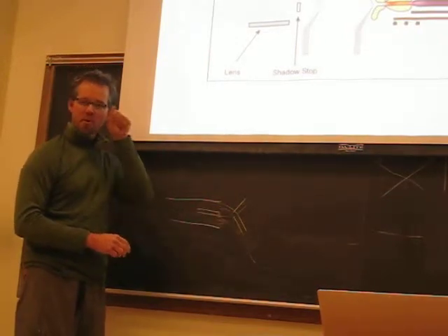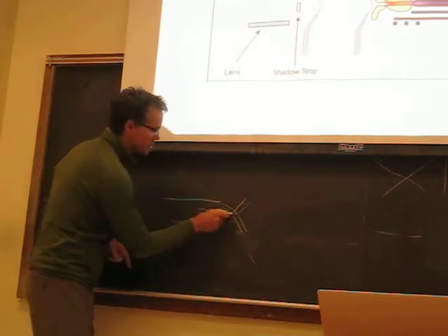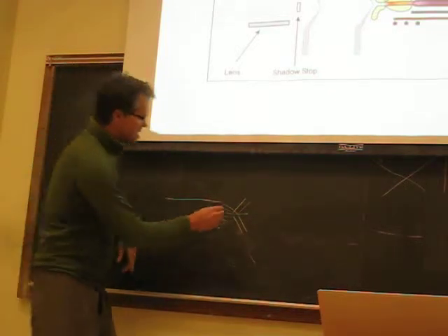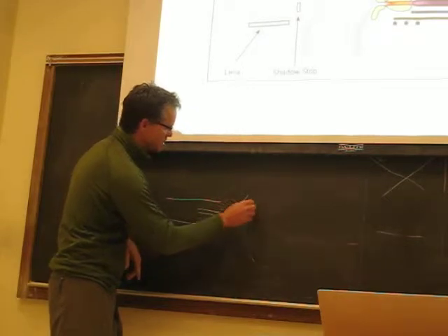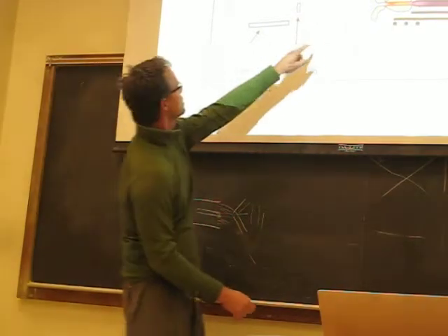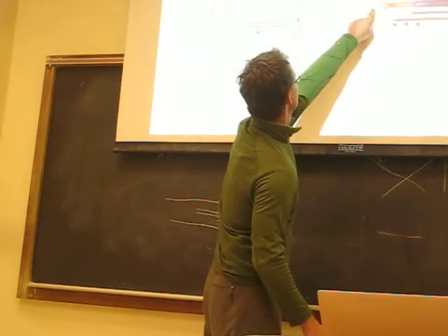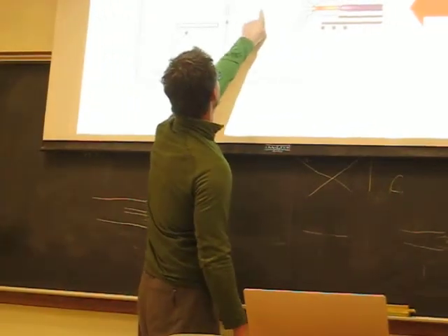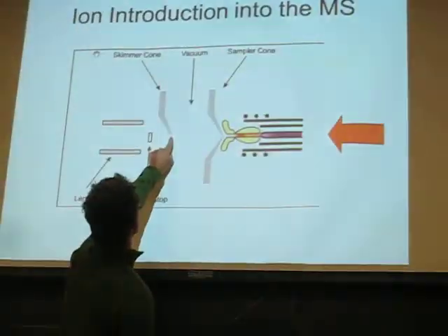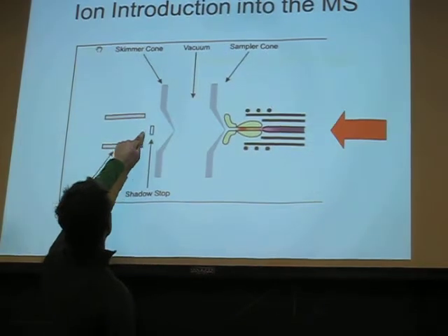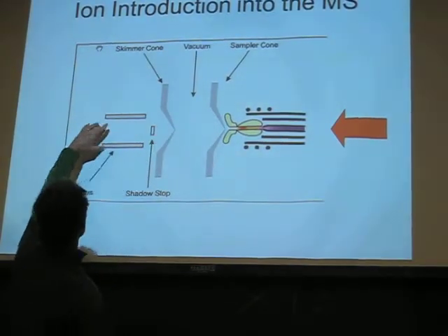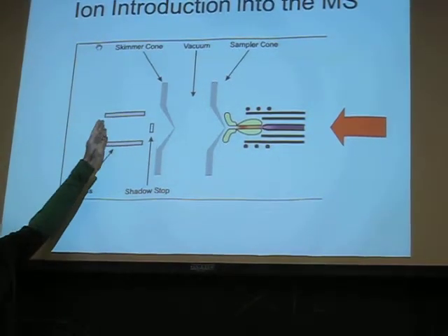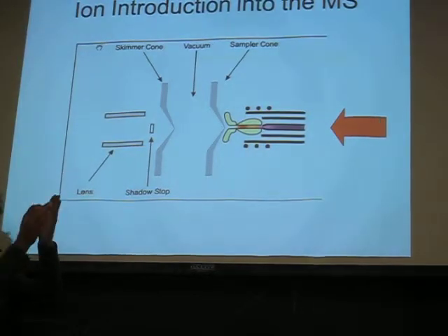It's a very small pinhole, and that's where your sample goes in. It has several of these cones, and they have electrical potential. Then it goes to these plates, and that's exactly what's shown here. The sample comes in through a small opening into a little bit of vacuum, this is removed, and then it flies into the electrostatic focusing lenses to accelerate and start focusing it.